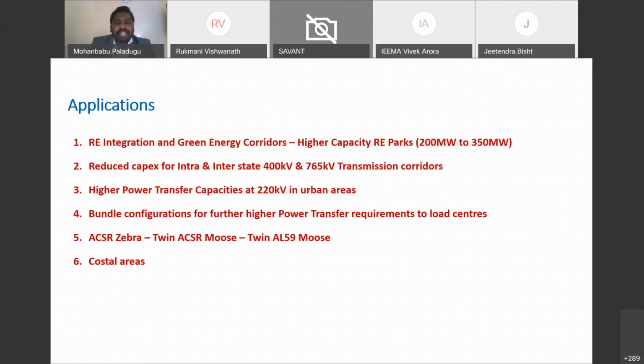And today, if we see in generally urban areas, load centers, there is a situation where we need to send higher capacities. And if you see planning criteria, we have also increased our maximum substation capacities. So to cater to these higher load centers or urban areas, traditional 220 kV lines in the cities, densely populated regions, are limited by their thermal capacities. So AL59 is one of the best alternatives here also. Then again, some of the utilities recently we are seeing coming up with bundle configurations at 220 kV.